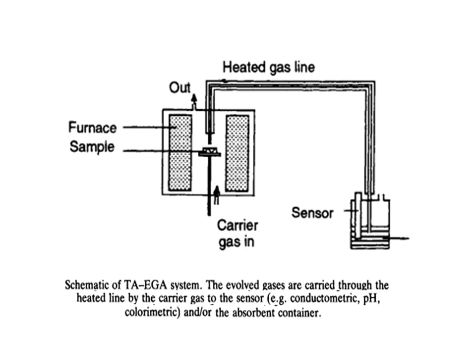Here is the schematic diagram of a thermogravimetry and evolved gas analysis system. There is a furnace compartment with a sample holder, a carrier gas inlet and outlet to maintain the internal environment. Heat is provided to the sample, changes occur, and products are emitted as gases. These gases move through a heated gas line into a compartment containing sensors — conductometric, pH, or colorimetric detectors — by which evolved gases are analyzed, or absorbers may absorb the gases for further analysis.